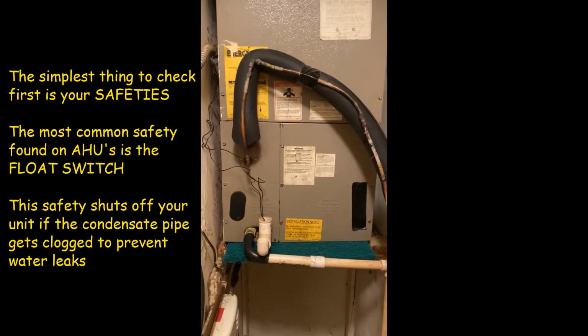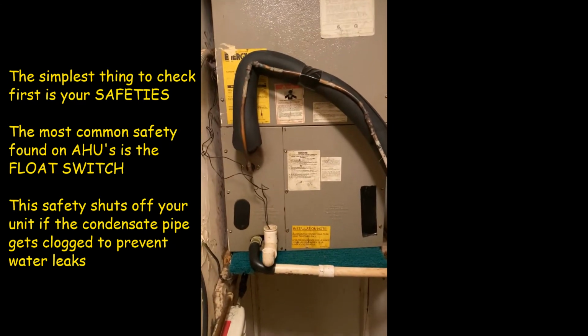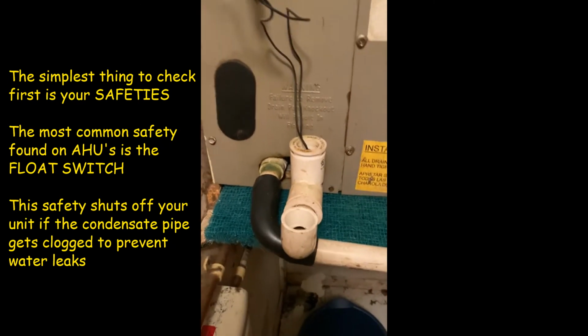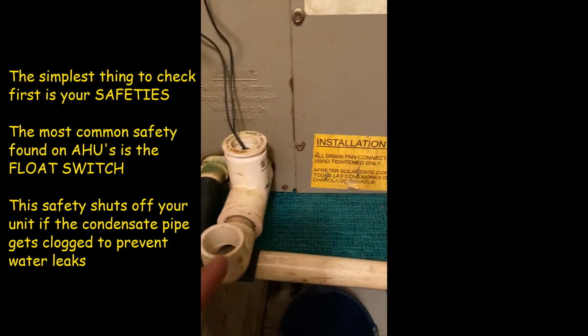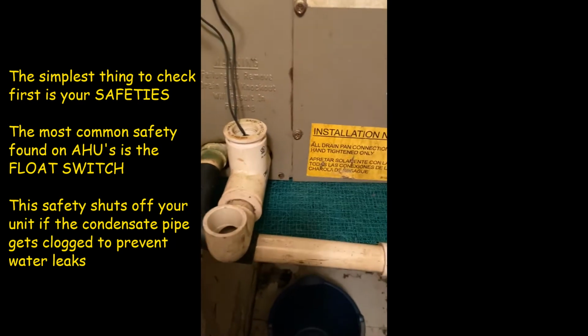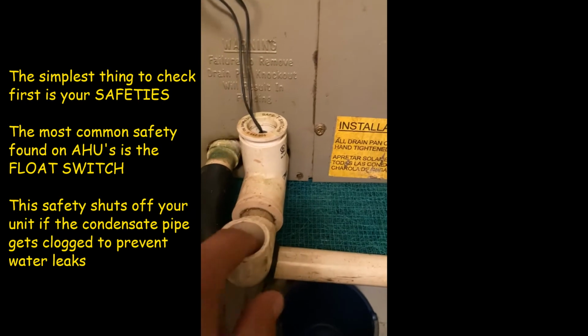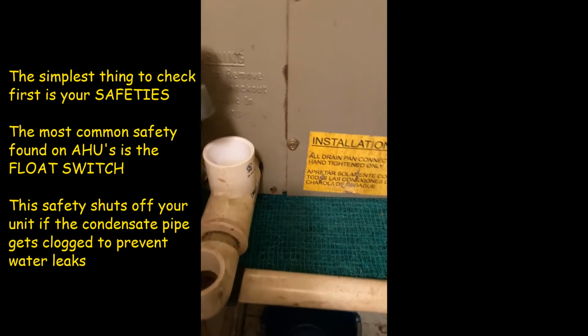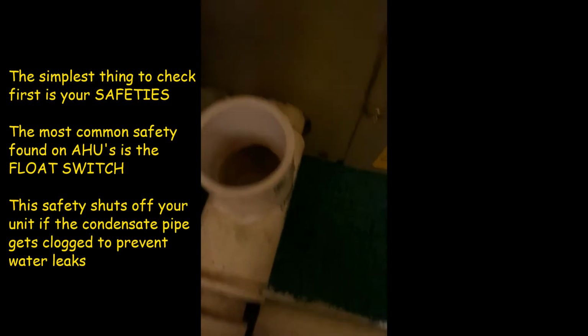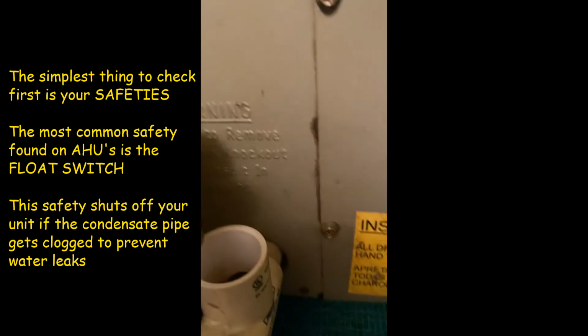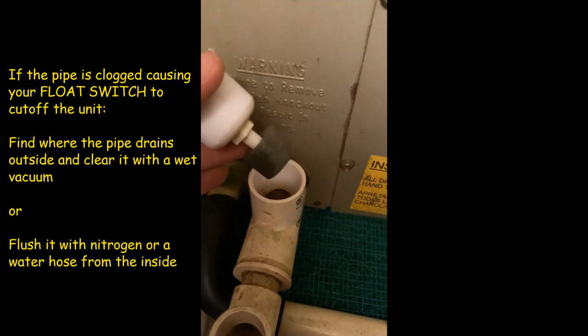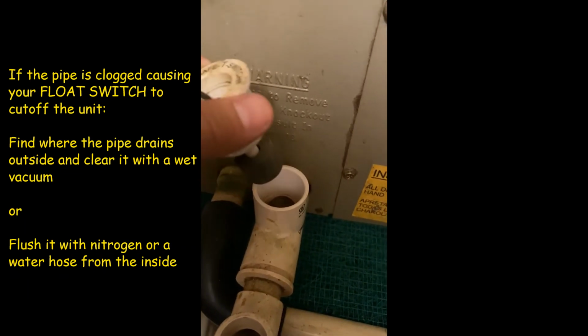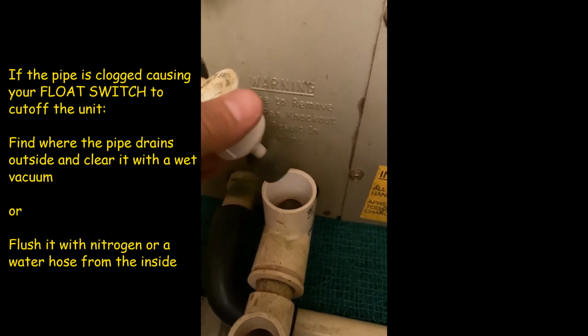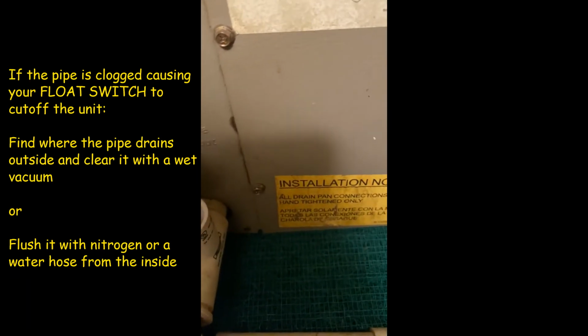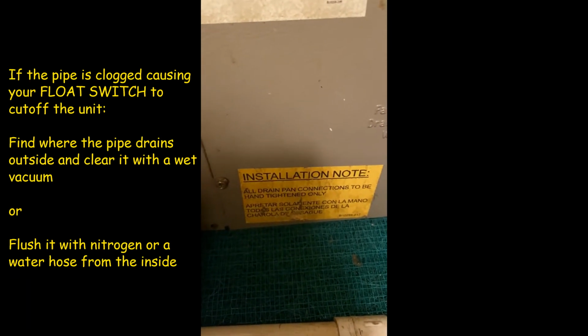So that'll tell you right away, okay, the problem is not a safety. But when you have a float switch, for example, which cuts off your unit if the pipe gets clogged so that you don't leak everywhere. If you got a float switch, that's the first thing you want to check. Check that there's no water in there. Be careful with them. You see here, no water. You know, this would be full of water pushing this little device up, cutting the unit off. But you know, if there's no water, this thing ain't even wet, that's not your problem. That's not what's breaking your control voltage.